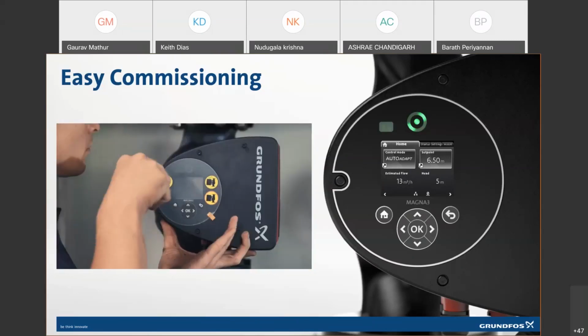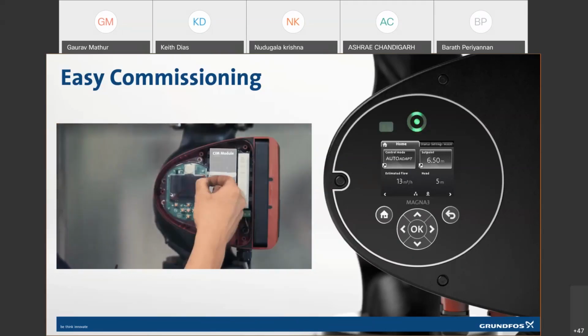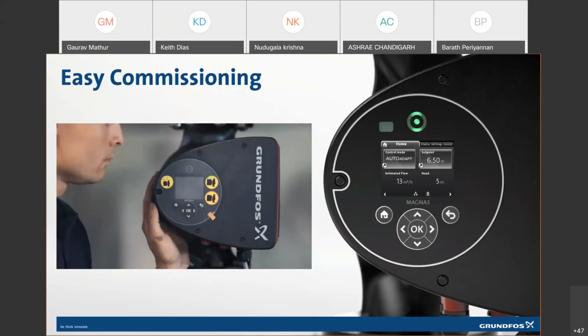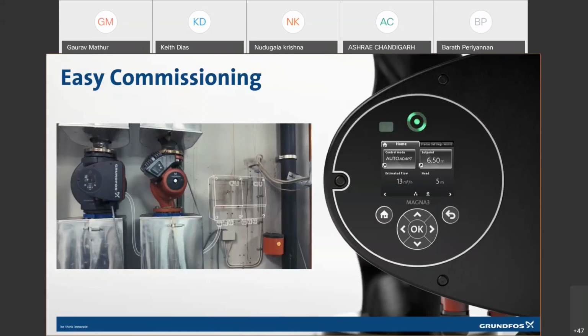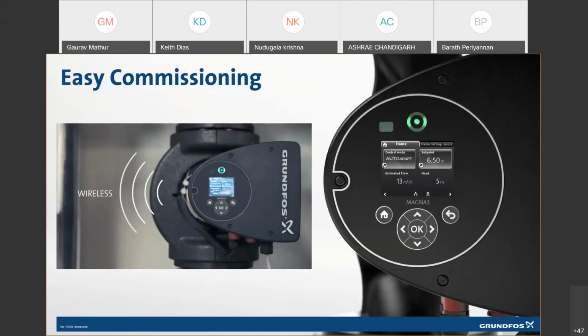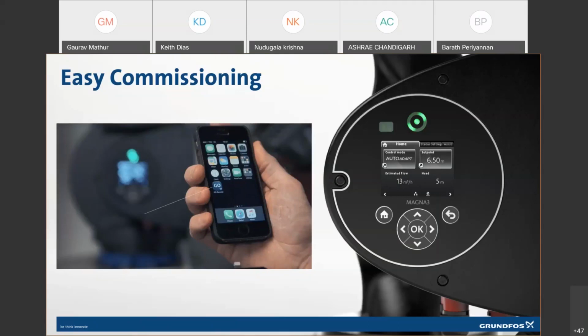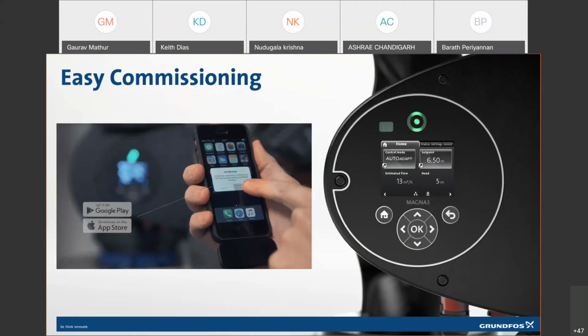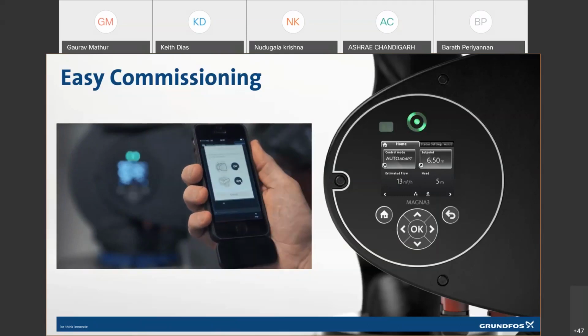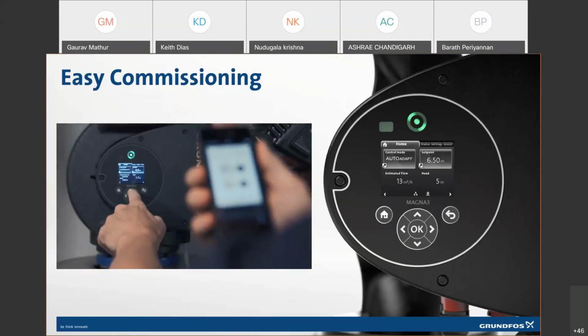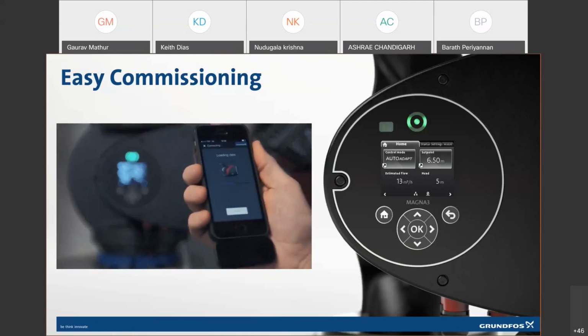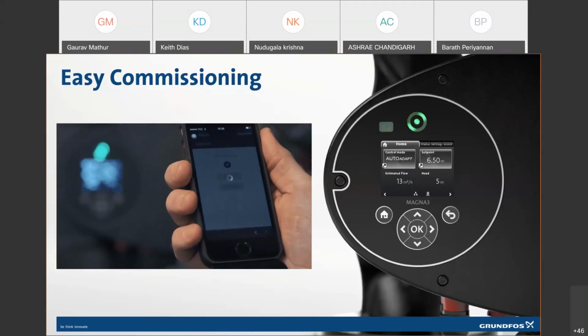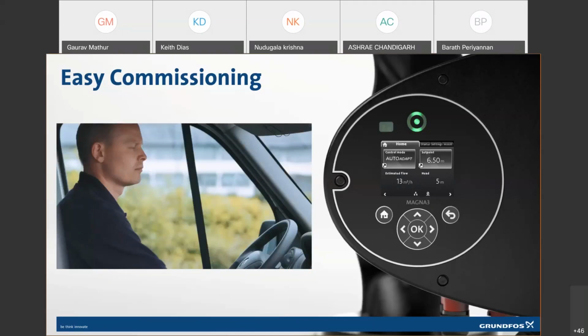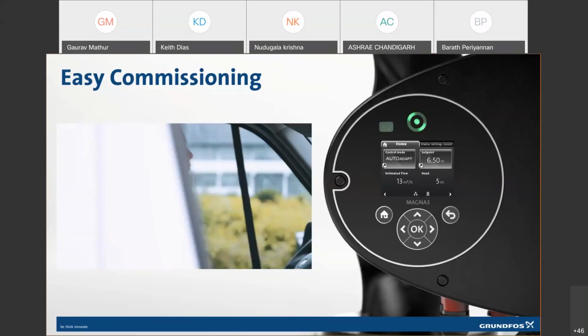If the pump needs to be connected to a control and monitoring system, all you need to do is put in the appropriate CIM module. This is easily done, and a huge improvement on the time when you had to mount a separate CIU box on the wall next to the pump. Another improvement from an installer's perspective is that the Magna 3 communicates via wireless radio. This means that you can now simply slide a dongle into your smartphone and set up the Magna 3 through the free Grundfos Go remote app. With the built-in startup guide, this will be quicker, easier, and a lot more comfortable than it used to be. And once you're done, you can even generate a report and send it to your customer on the spot. Job done. That's how you make your big customers happy, without even breaking a sweat.